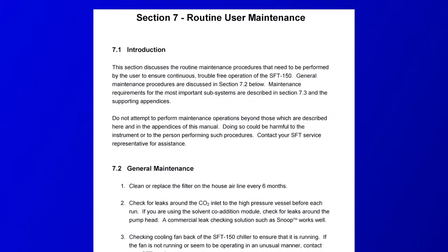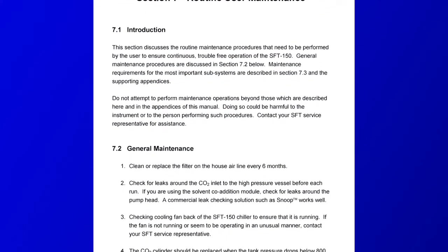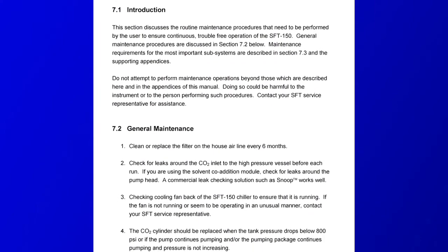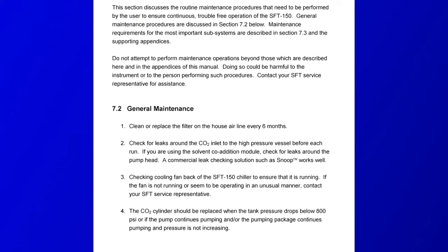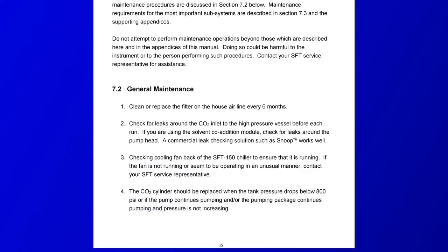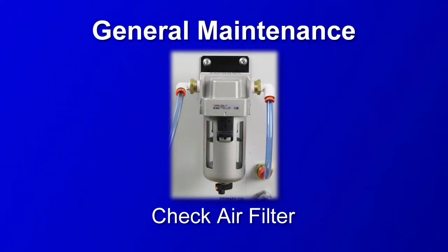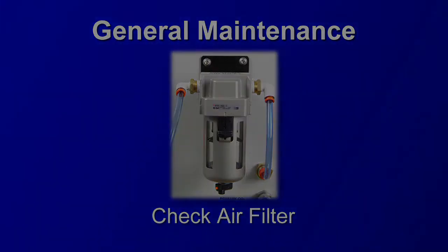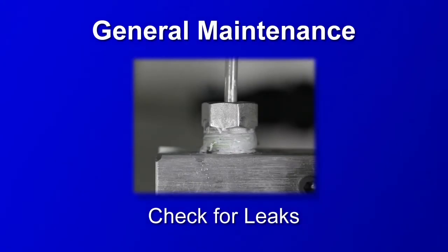Maintenance. Routine maintenance items are discussed in detail in Section 7 of the user manual. Unless otherwise directed by SFT, do not attempt to do any maintenance beyond what is discussed in the user manual. General maintenance items. Check the air filter every 6 months. Flush away any water or oil that has accumulated. Replace if dirty.